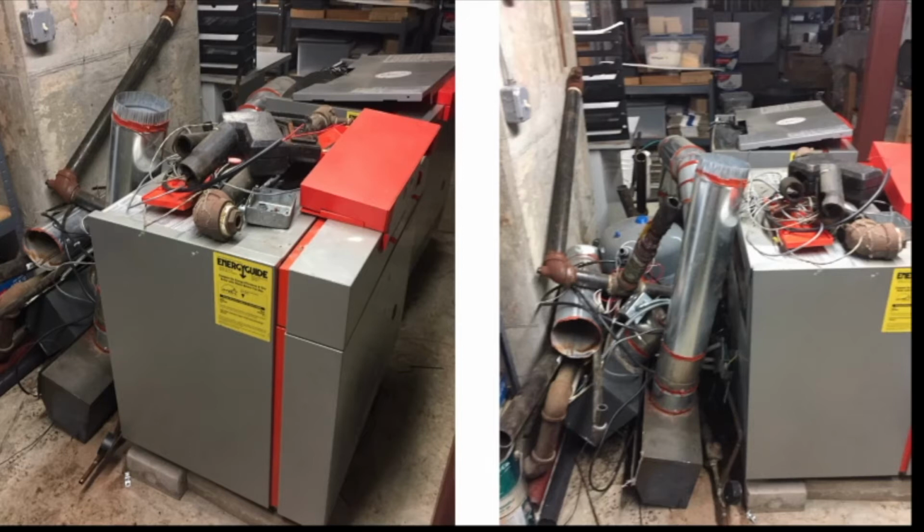The winter relative humidity levels were controlled by dropping the indoor temperature to a minimum of 50 degrees Fahrenheit because it was about the lowest temperature that anybody could really stand while still working in there. Humidity could not be added due to concerns about condensation in the uninsulated walls. The boilers also had a really large fresh air makeup system that contributed to the winter dryness.